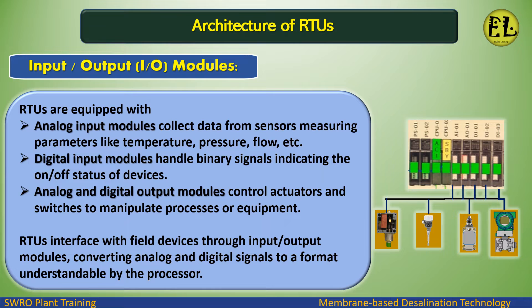RTUs are equipped with input/output (I/O) modules. Analog input modules collect data from sensors measuring parameters like temperature, pressure, and flow. Digital input modules handle binary signals indicating the on/off status of devices. Analog and digital output modules control actuators and switches to manipulate processes or equipment. RTUs interface with field devices through these I/O modules, converting analog and digital signals to a format understandable by the processor.